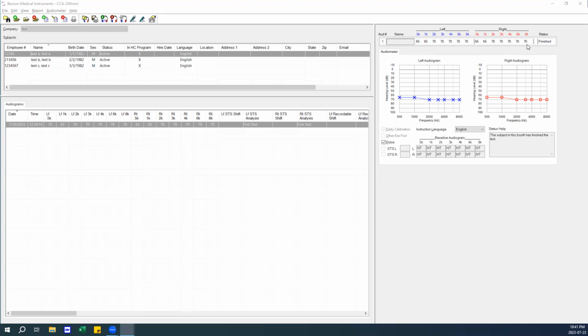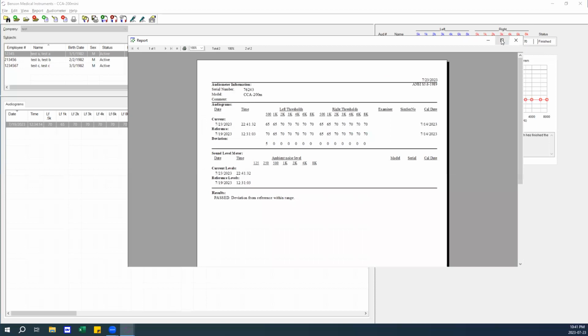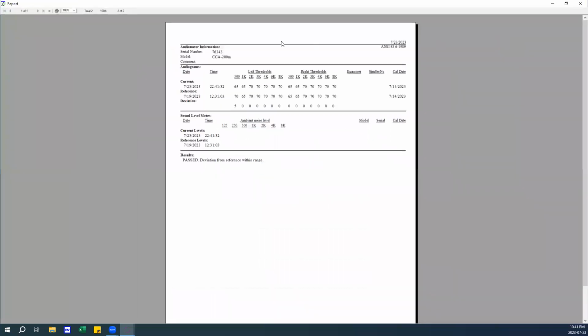Now that the collection is complete, the status should say finished. Then we should get a printout, print to screen. And from here, you can see that there is a slight deviation from our reference, which is what essentially the machine wants to capture. So in this case, captured 65. What it was looking for was 70.